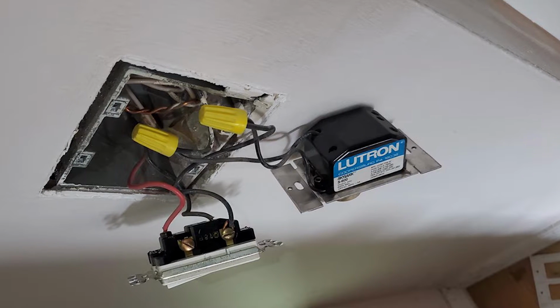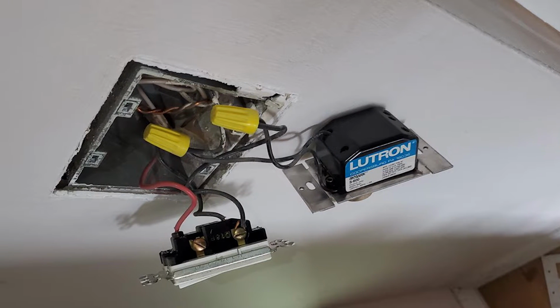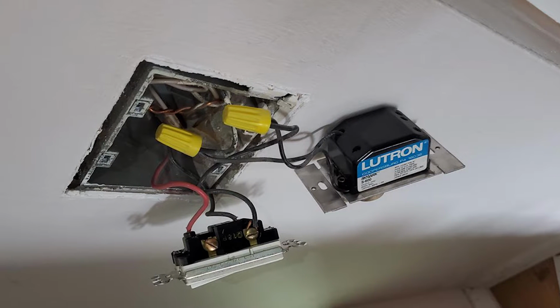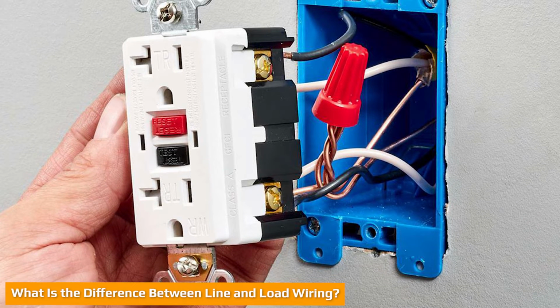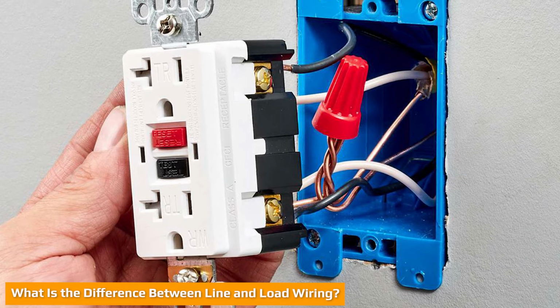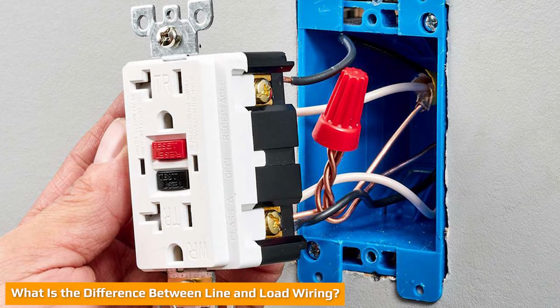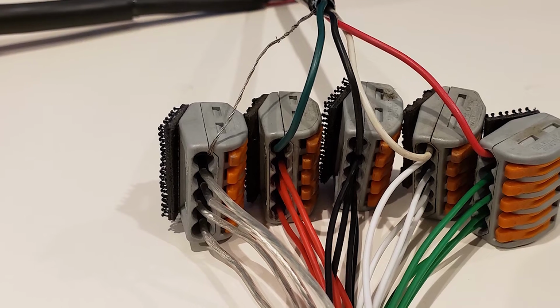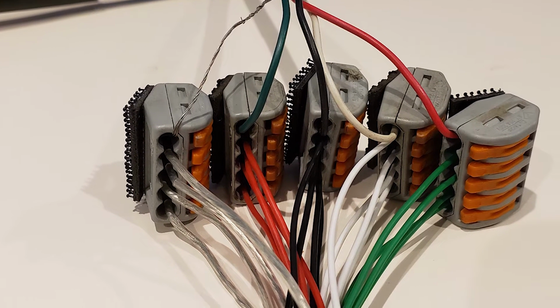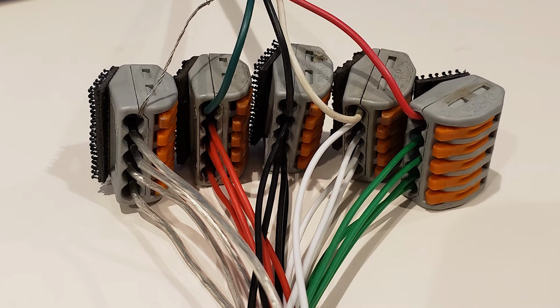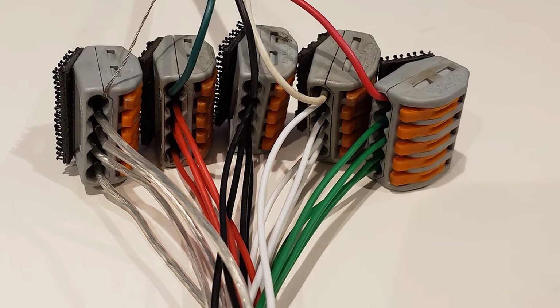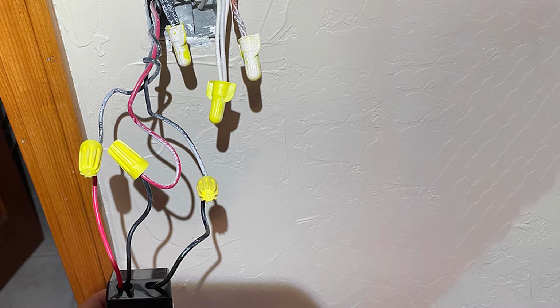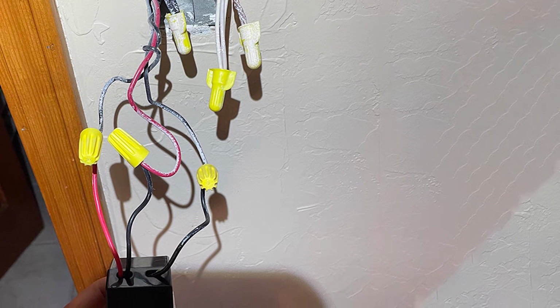The terms line and load have a number of applications at different locations in an electrical system. The incoming feed from the utility company comes into the line side of an electric meter. It leaves the meter from the load side and then feeds the line side of a disconnect or electrical service panel. The service panel also has line and load connections. The line feeds the main breaker in the panel, while the individual branch circuit breakers can be considered the load with respect to the main breaker.